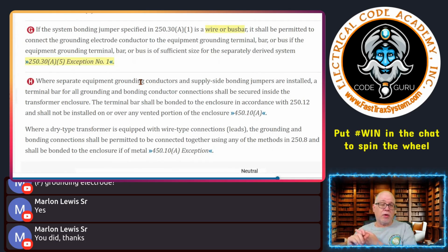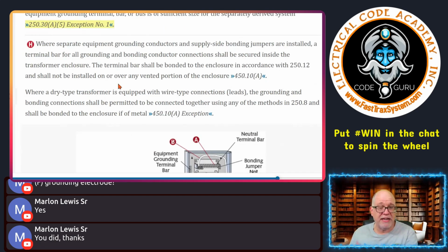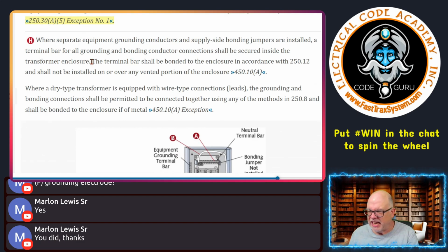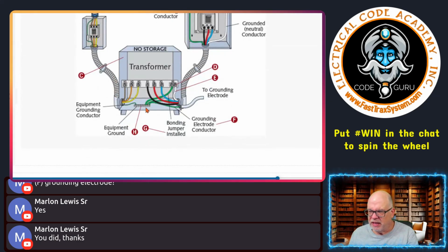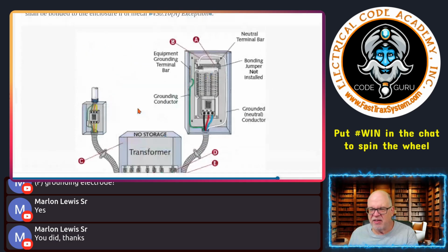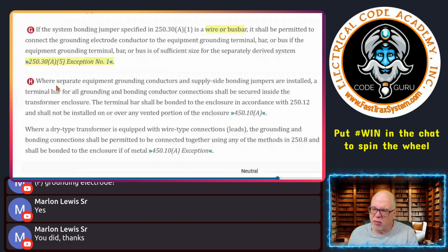Folks, that's why it's so important, if you're in a fast track system, that you stop and go read those exceptions, or read how the code reads. All right, lastly, H, we'll cover H and I'll spin the wheel. So here's that bus bar we're talking about right here, again not mounted on the ventilation holes. It says, where separate equipment grounding conductors and supply side bonding jumpers are installed.